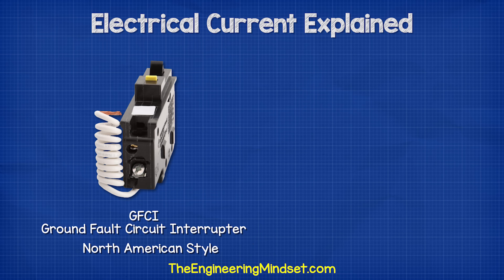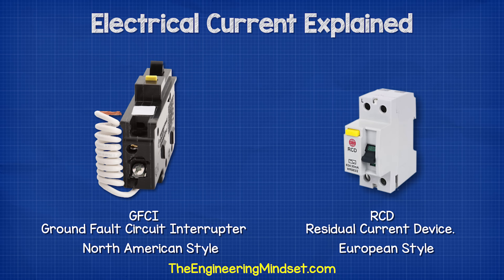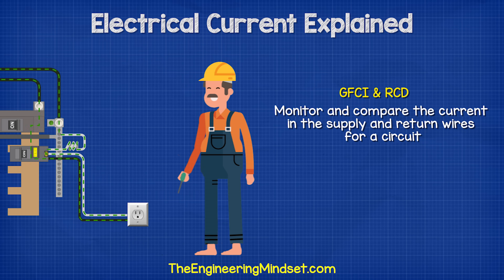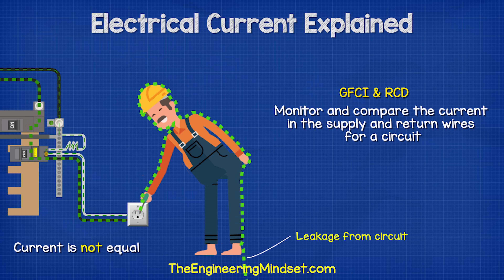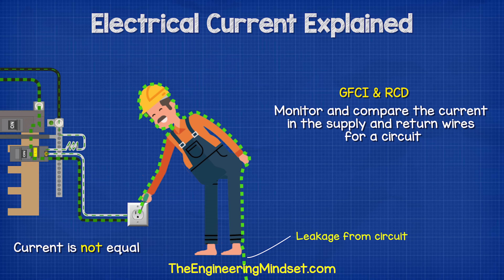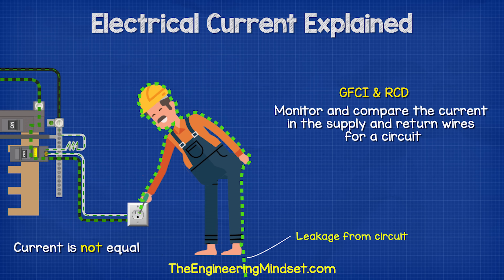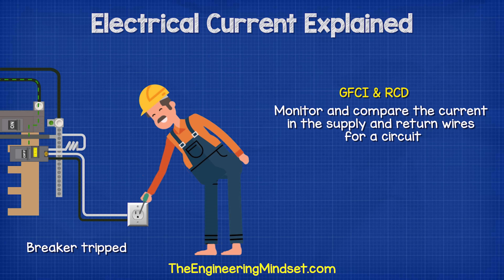In North America, we find another device called a GFCI, or a ground fault circuit interrupter. In Europe, this is called an RCD, or a residual current device. These basically monitor and compare the current in the supply and return wires to a circuit. If the current coming back is not equal to the current being supplied, then the electricity has found another path and is leaving the circuit — it could be passing through a person, so the device cuts the power. This happens extremely fast and with a very small tolerance to help protect against electric shocks and keep us safe.